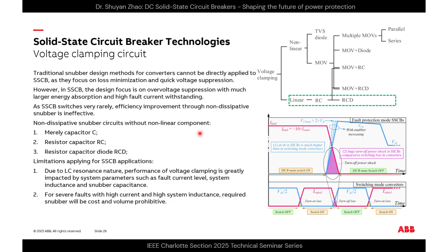So non-dissipative snubber circuit without nonlinear components, merely like capacitor or RC or RCD. Those are very common power electronics knowledge, right? So the limitation applying to solid state breaker application is due to the LC resonance nature. The performance of voltage clamping is greatly impacted by system parameters like current level, system inductance, and snubber capacitance. And they are dependent on each other. It's LC resonance, right? So for severe faults with high current and high system inductance, the required snubber will be cost and volume prohibitive because that will need a very large capacitance.